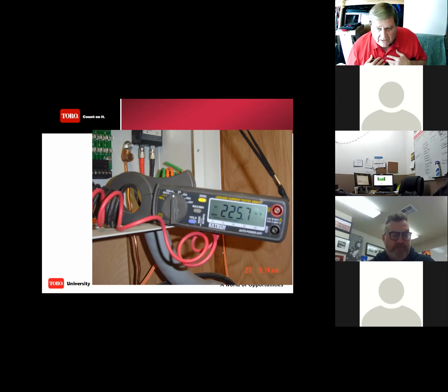I ohm check the 2-wire path at this point. It's not connected to the clock, it's been removed. What's the resistance on that wire? On a good 2-wire system, your resistance should be open. Very important. The resistance on a standard, typical 2-wire path, the resistance is open. If you're reading a short circuit, 10 ohms or less, you have a short in that system and do not connect it to the clock because you're going to blow the fuse again.